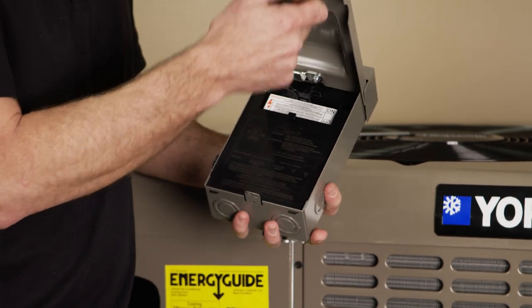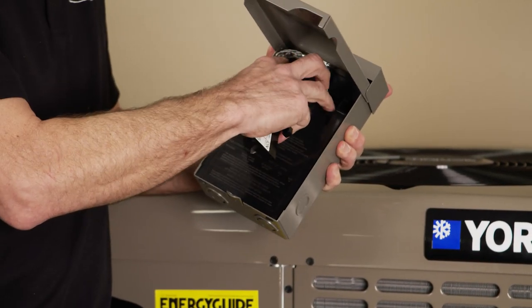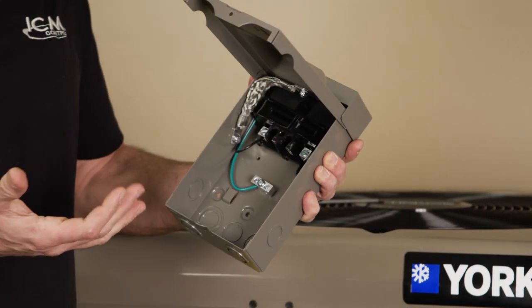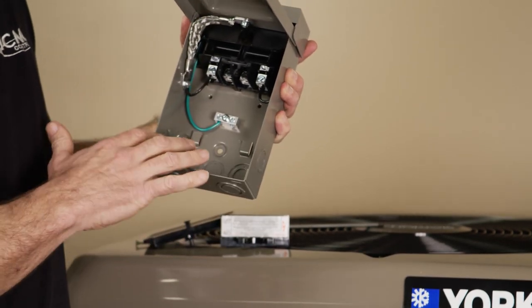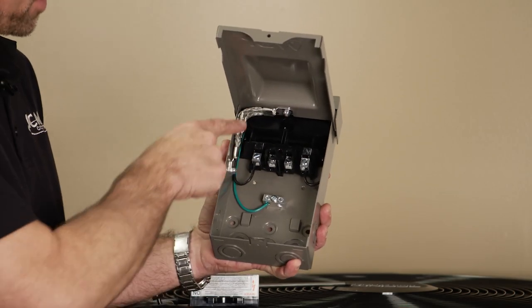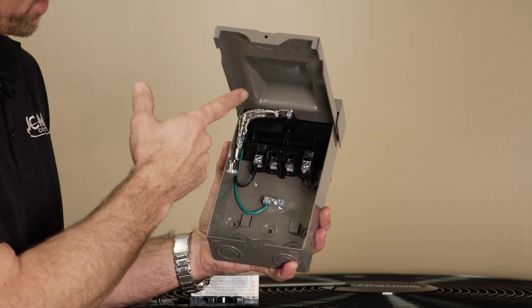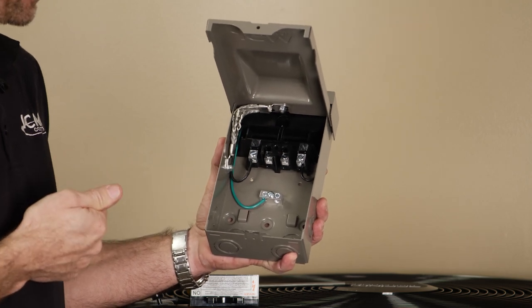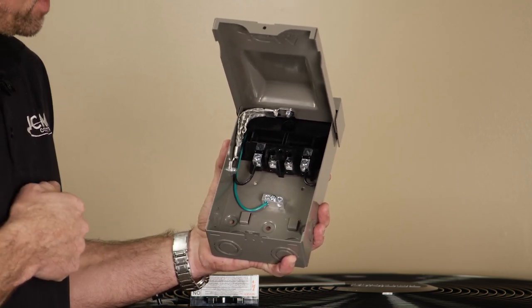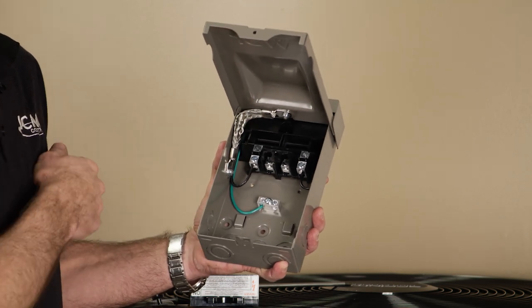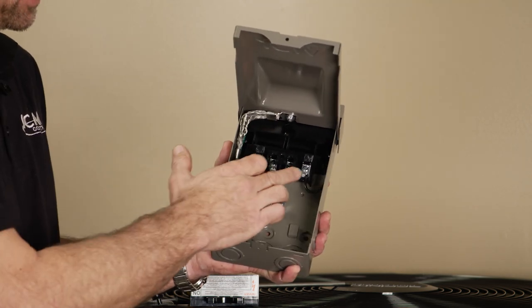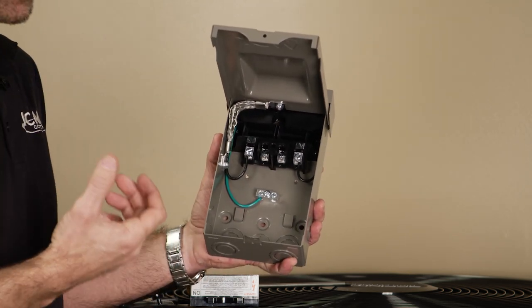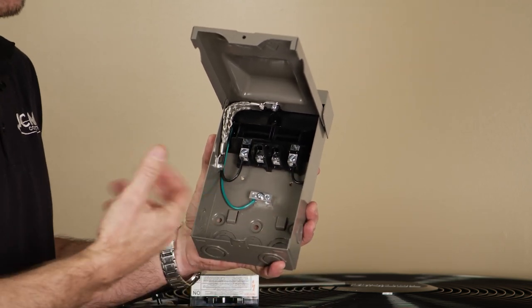So internally, with the non-fuse disconnect version you'll see it's wide open, there's plenty of room to access the mounting holes. In the upper section here you'll see the field replaceable surge protector which has a best-in-class maximum surge protection rating of 100,000 amps. It is constructed with two high quality TMOVs. As you can see here it is factory wired so you don't have to do anything extra. As with some of the competitors you actually have to take a knockout out and wire it in yourself.